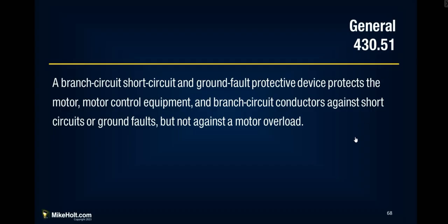So a branch circuit, short circuit, and ground fault protective device protects the motor, motor control equipment, and branch circuit conductors against short circuits or ground faults, but not against a motor overload. You have to understand the difference between overcurrent and overload. I always use the analogy that overcurrent is short circuit or ground fault protection. In other words, when you have two hot wires come together, or a hot wire and a grounded conductor or the neutral come together, that's a ground fault, short circuit type scenario.